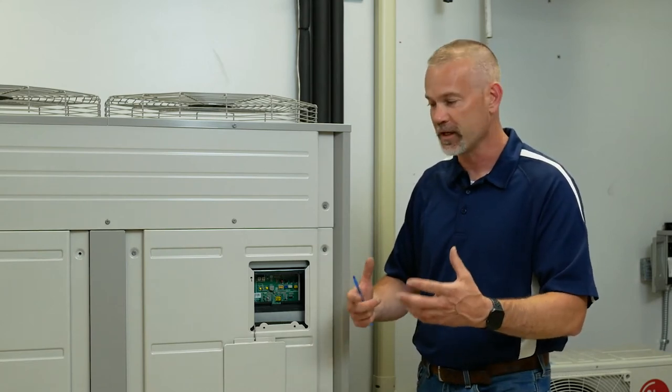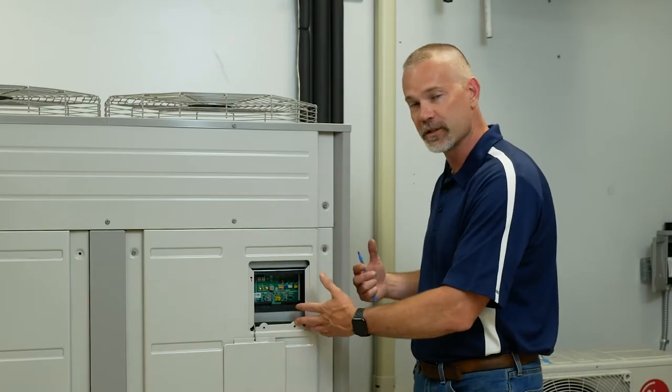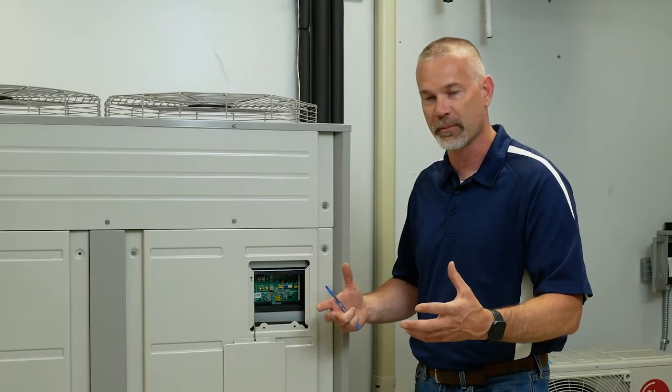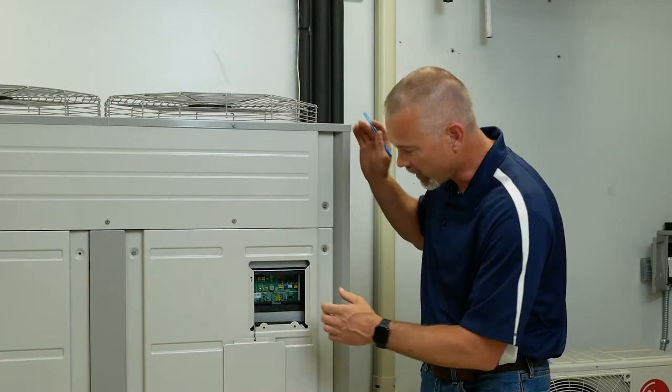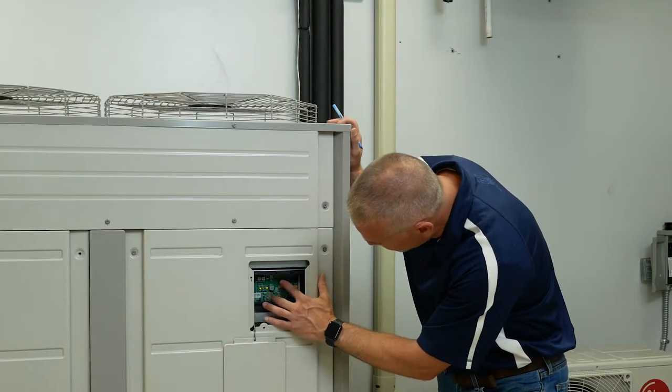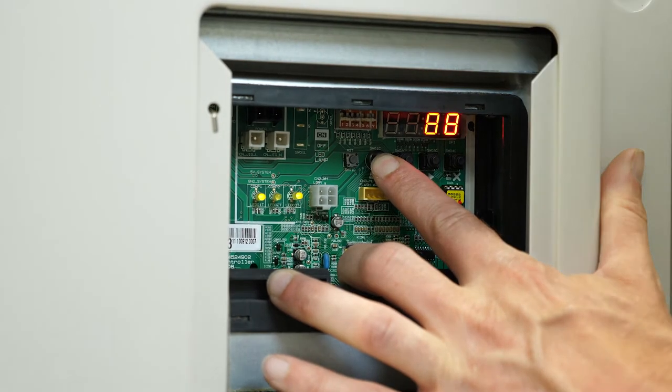Everything has to be powered up. Nothing can be calling—none of your indoor units can be calling for heating or cooling. All your power supplies have to be intact, and if we're doing a heat recovery system, your HR boxes have to be configured at that point. We're going to hold that red button here for three to five seconds.